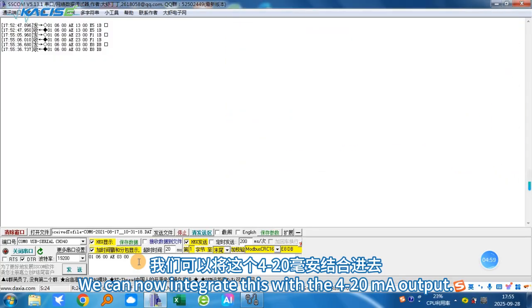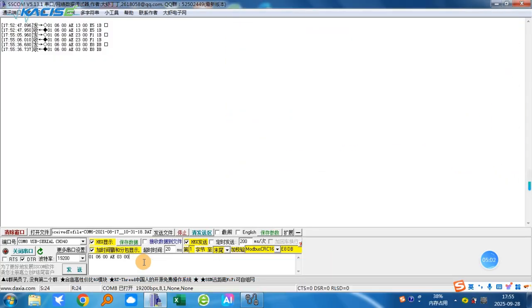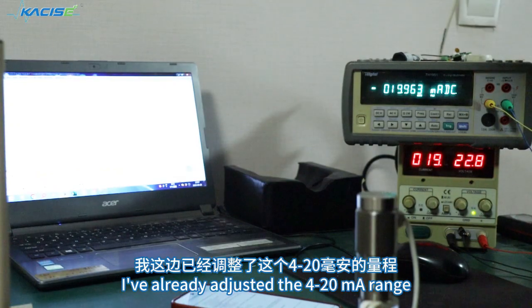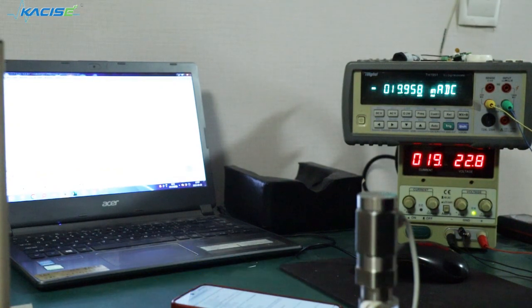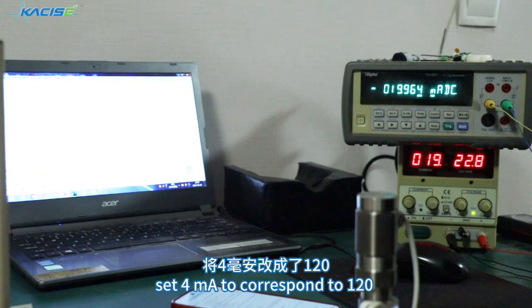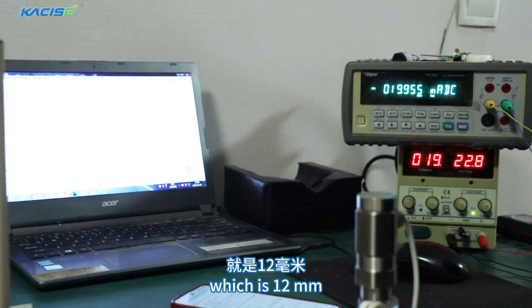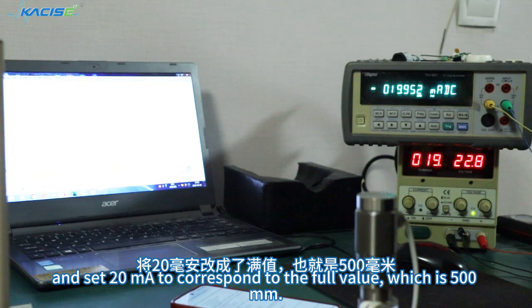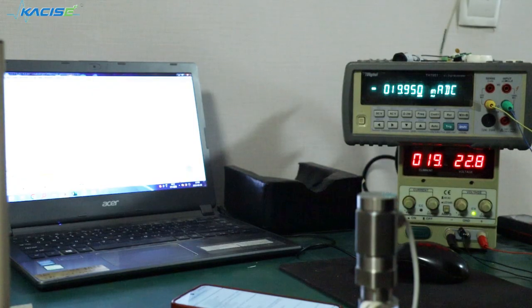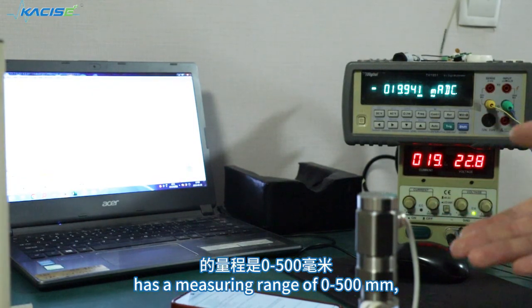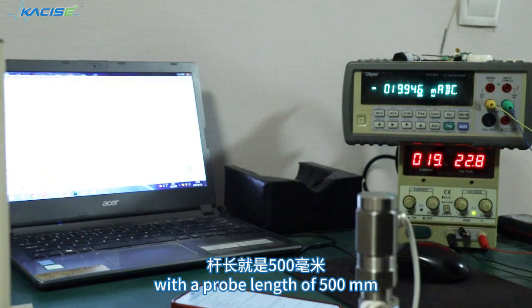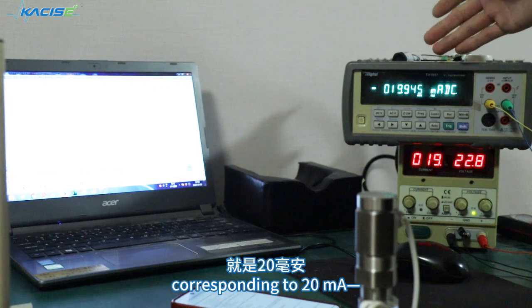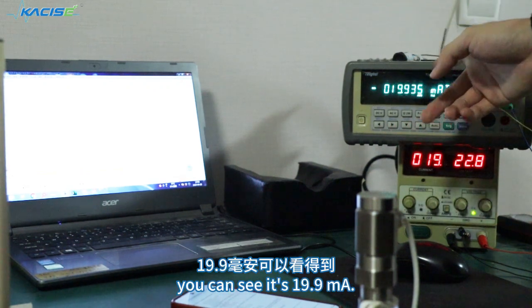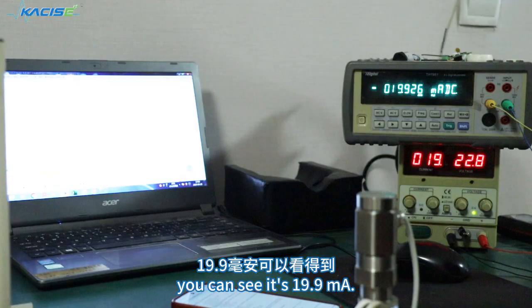We can now integrate this with the 4 to 20 mA output. I've already adjusted the 4 to 20 mA range. Set 4 mA to correspond to 120, which is 12 millimeters, and set 20 mA to correspond to the full value, which is 500 millimeters. Because this sensor has a measuring range of 0 to 500 millimeters, with a probe length of 500 millimeters, our current liquid level is full, corresponding to 20 milliamperes. You can see it's 19.9 milliamperes.